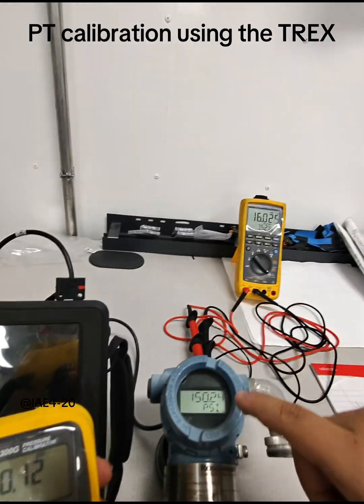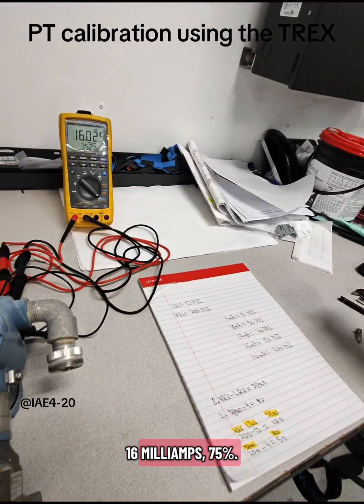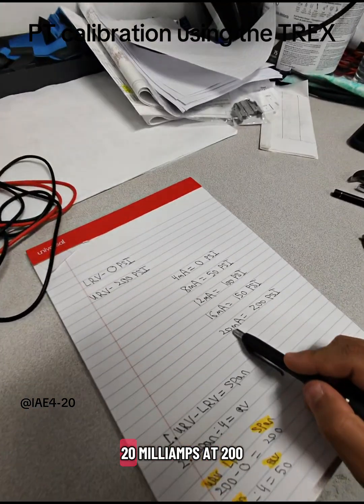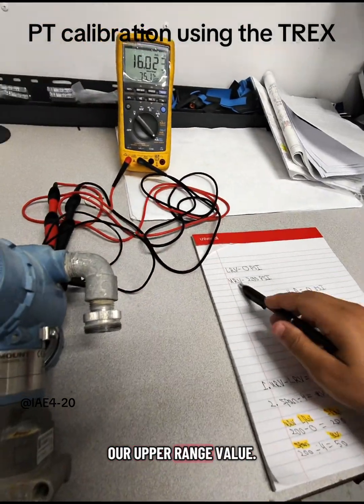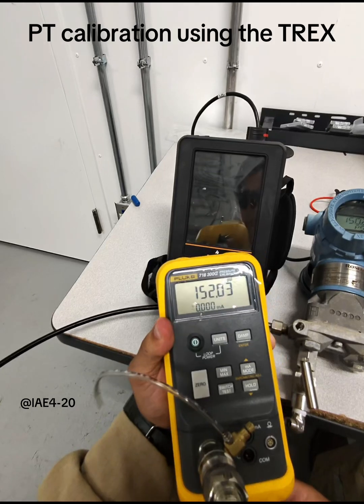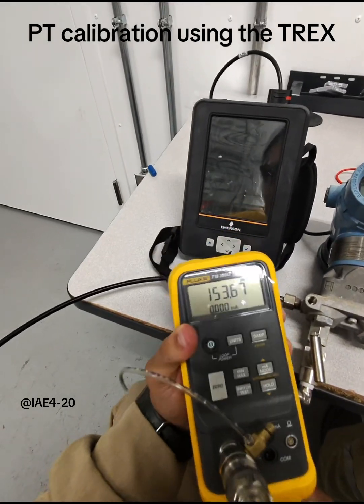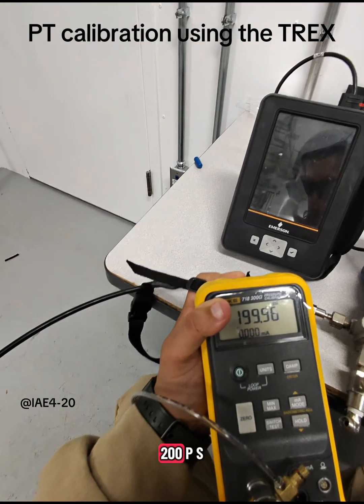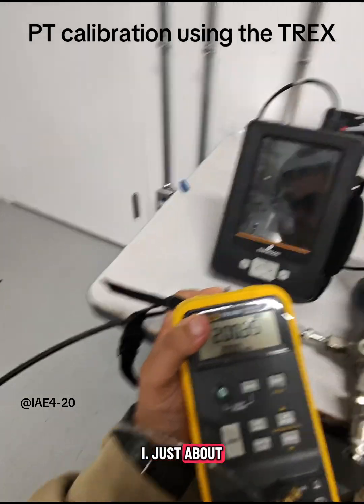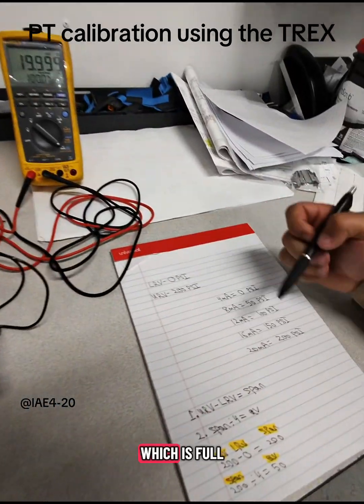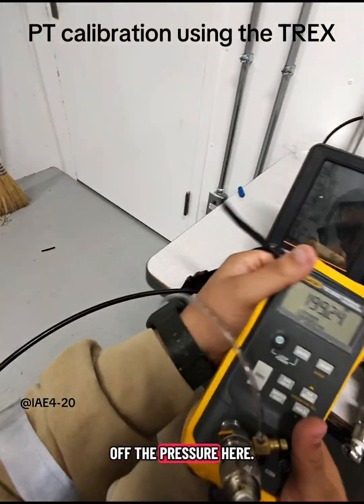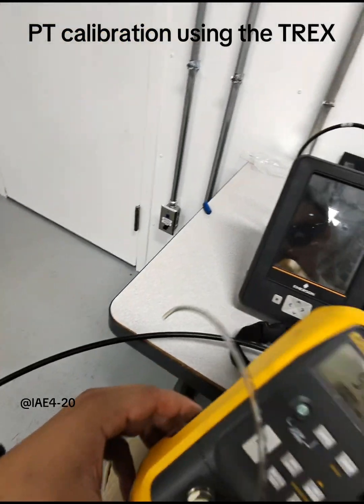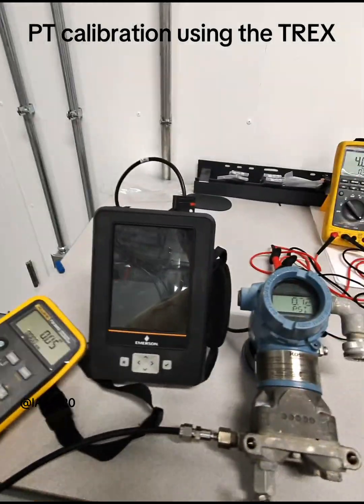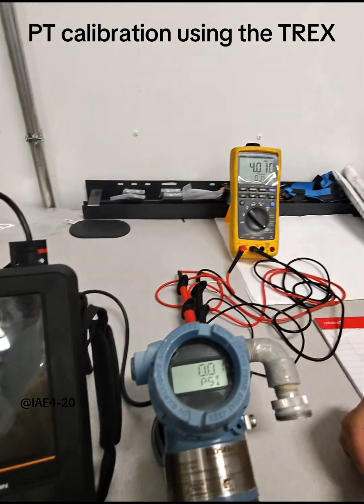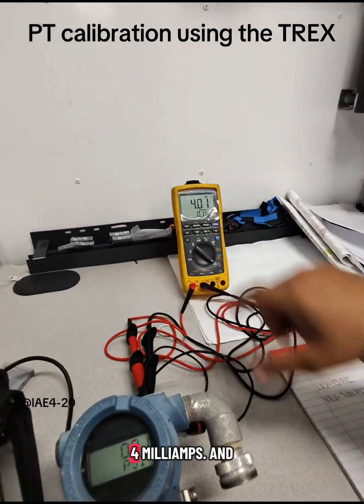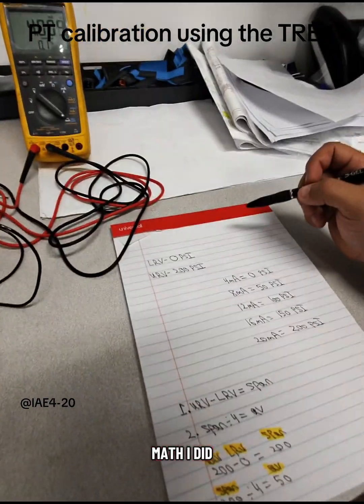150, 16 milliamps, 75%. Now we're going to go full scale, 20 milliamps at 200 psi. It's going to be our upper range value. Now we're at 200 psi, just about. We're reading about 20.02 milliamps, which is full scale. We'll go ahead and bleed off the pressure here. Take it back down to 0. See what our 0 is reading here. 0.01 psi, 4 milliamps.